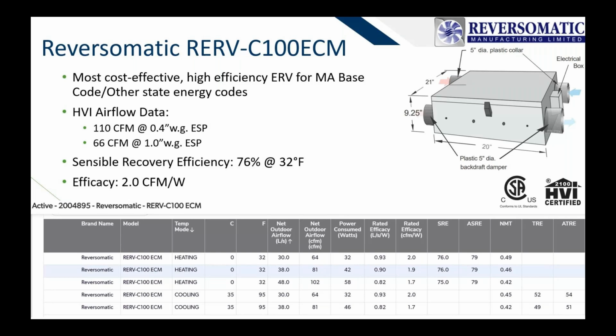Somebody asked, do these need drains? No, these do not need drains. Everything that I've shown you so far is an ERV, or an enthalpy recovery ventilator. So the only time you really would need a drain is if it's an HRV, which we don't typically like to sell in our market because it does get to be a high humidity area, and you end up with condensation that you do need to drain out. Now, it's not impossible. You can absolutely use an HRV. Just know that you need to accommodate those drains. Good question.